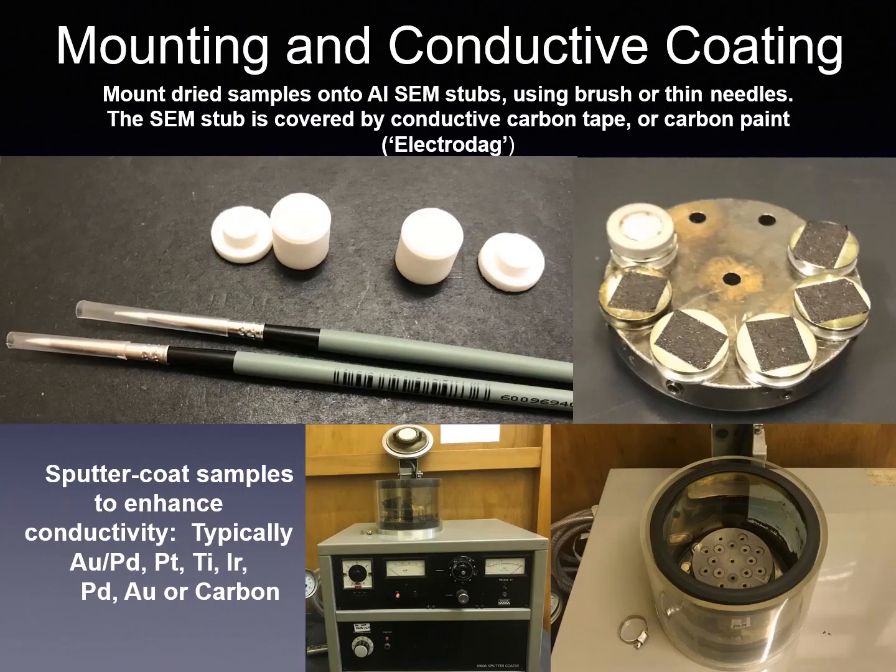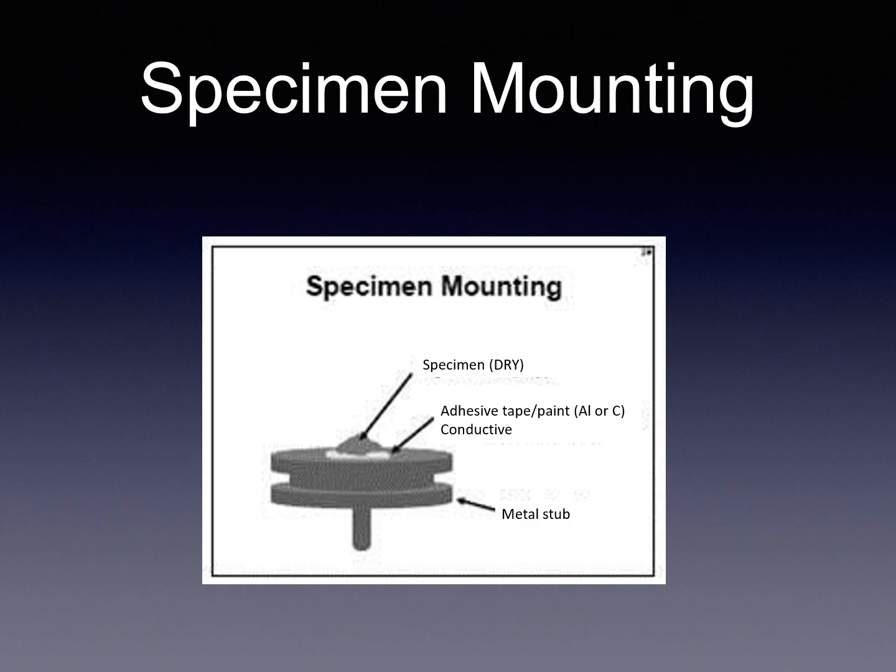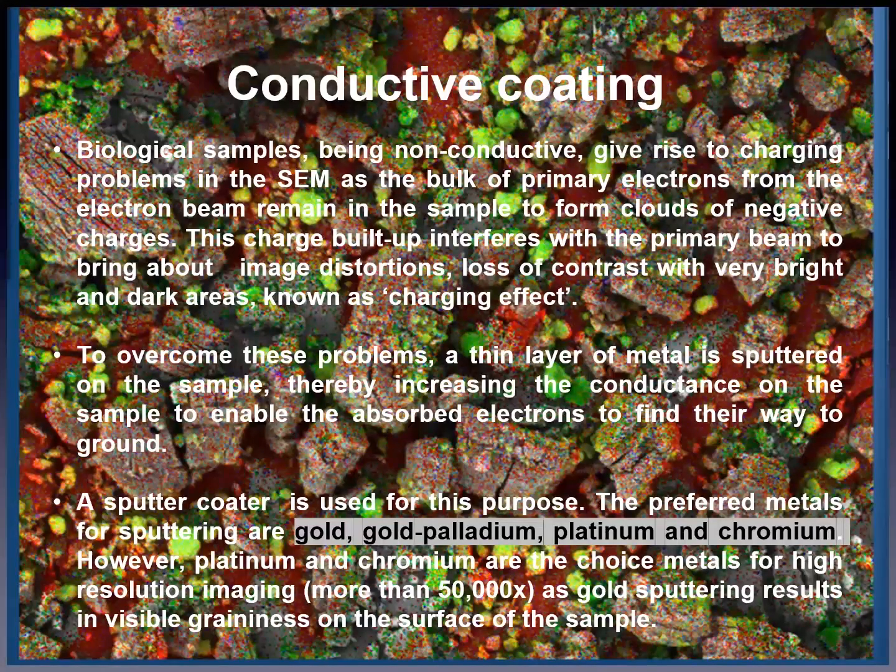Sample mounting and conductive coating: mount dried samples on aluminium SEM stubs using a brush or thin needles. The SEM stub is covered by conductive carbon tape, carbon paint ('Electrodag'). Sputter coat the sample to enhance conductivity, typically with gold, gold-palladium, or another metal or carbon. Biological samples being non-conductive give rise to charging problems in the SEM, as the bulk of primary electrons from the beam remain in the sample forming clouds of negative charge. This charge build-up interferes with the primary beam to bring about image distortions and loss of contrast with very bright and dark areas, known as the charging effect. To overcome these problems, a thin layer of metal is sputtered on the sample, increasing conductance to enable absorbed electrons to find their way to ground.